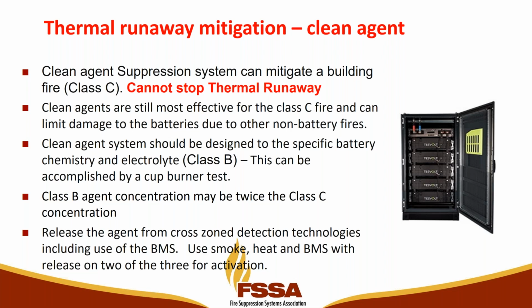And one of the things is how do you release? We're looking at multiple levels, possibly smoke. Generally, smoke is too late. Heat, BMS, while not listed, is a very good indicator of where there's failure modes happening. I can tell you that you've got some stray voltage, that you've got some heat conditions that may lead you to a fire. So I would never release on that, but it's not a bad indicator for your fire panel to pick it up.